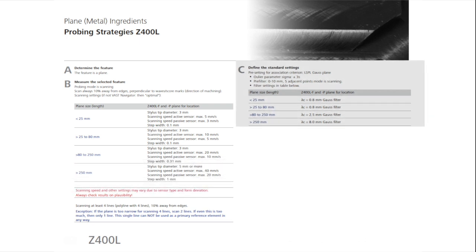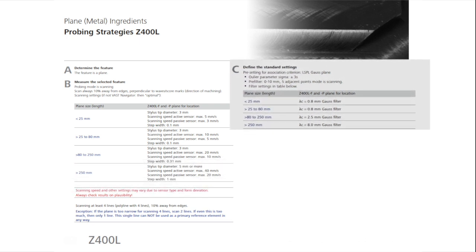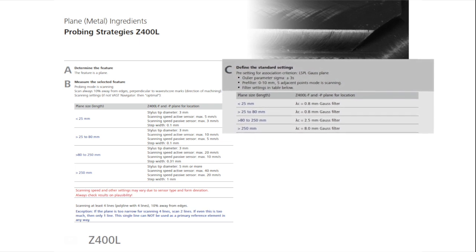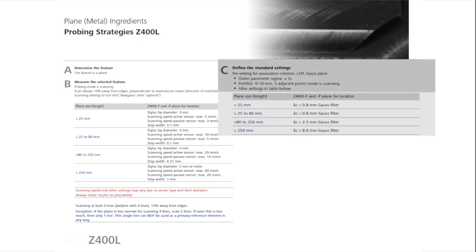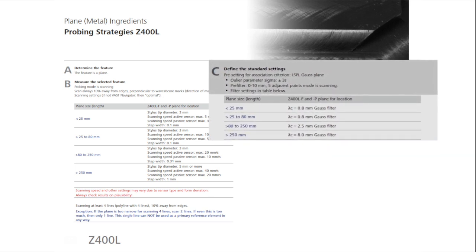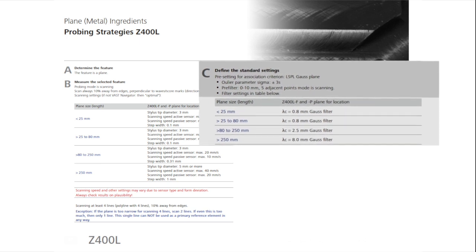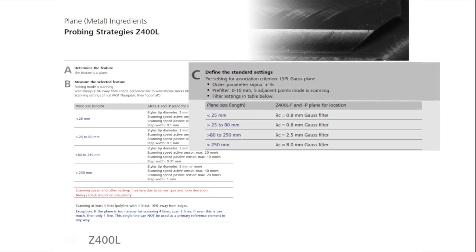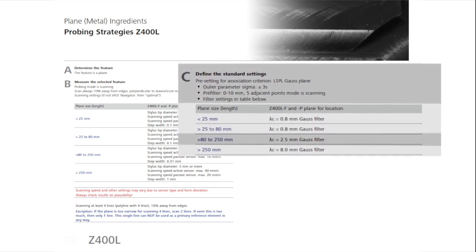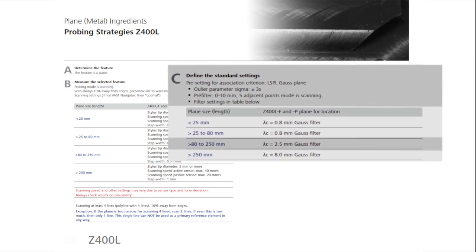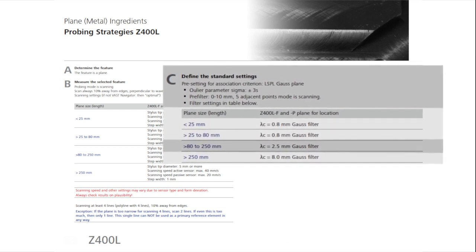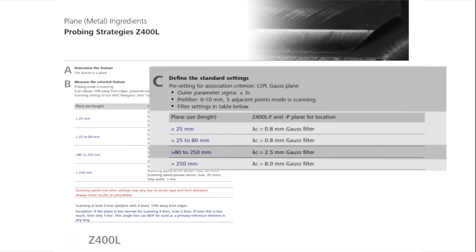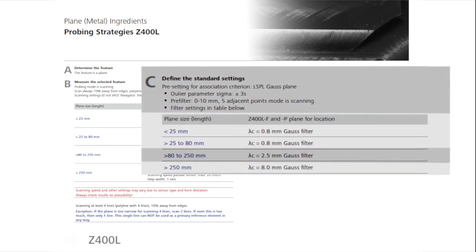The plane should be evaluated with outlier elimination, setting the parameters of sigma at plus and minus 3, and with 5 adjacent points, and pre-filtering at 0 to 10 lambda C. In the table, you will also find the settings for the recommended Gauss filter, in this case, set at a wavelength lambda C of 2.5 mm.